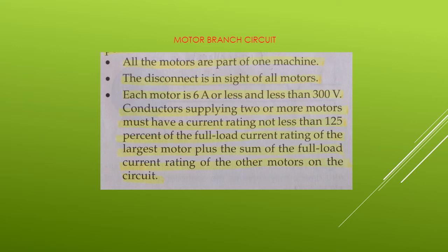The disconnect is in sight of all of the motors, and each motor is 6 amps or less and less than 300 volts. Conductors supplying 2 or more motors must have a current rating not less than 125% of the full load current rating of the largest motor plus the sum of the full load current ratings of the other motors on the circuit.